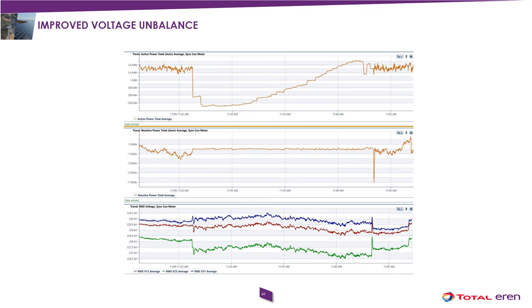Now, I thought I might just jump to something a little bit different. Here's some operational data from the Syncon, and I'd like to just demonstrate, even though the rules define system strength in terms of fault level, here we can see an attribute of a stronger system, and that's improved voltage balance. So if you just follow along, here's where the Syncon is turned off, and here's approximately where it's turned on again. So now we direct our attention to the bottom graph and look at the line-to-line voltages. During the time when the Syncon is on, you can see the approximate distance between the phases, and then when the Syncon is off, and then when it's on again. So I thought it's a bit of a neat visualization of an attribute of a stronger system.